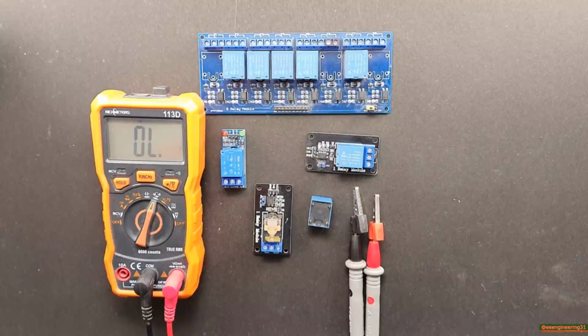Now let's see how to repair a relay. Relays are failure prone, especially with age, and finding an exact replacement can be tough. When substituting relays, the most important specifications are the coil voltage and the current handling capacity of the contacts. Naturally, you need the relay to have the same number of poles and throws as well, so that it fits in the original place. The current required for the coil to pull in the relay also matters, but there is some leeway. Sometimes it won't be specified on the relay, but you might be able to find it from the part number by looking it up on the internet.